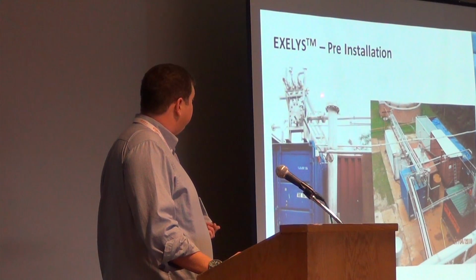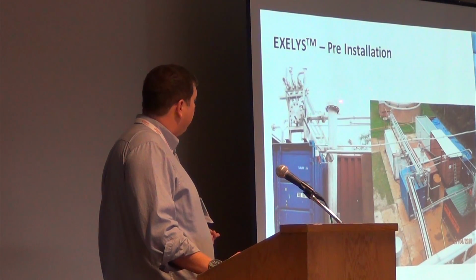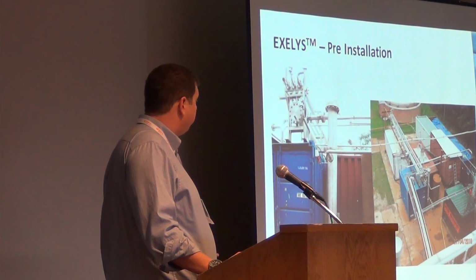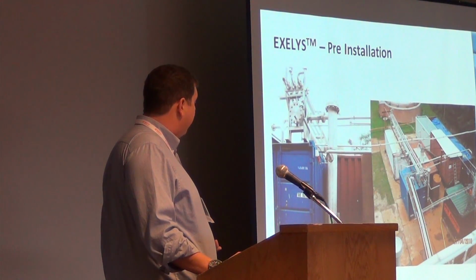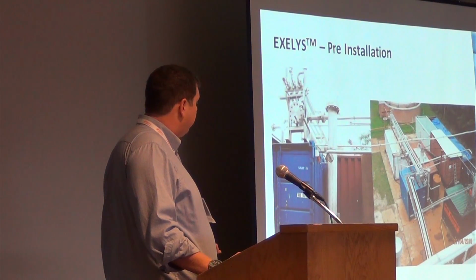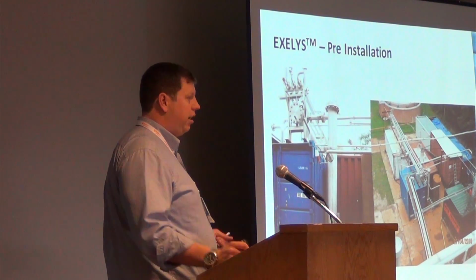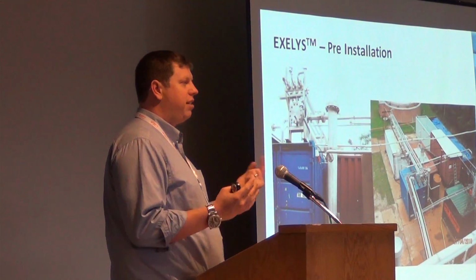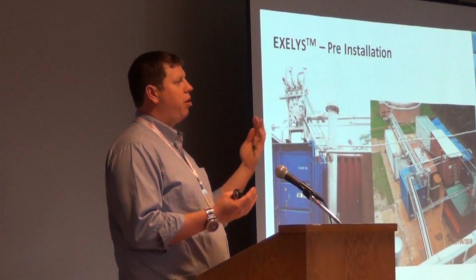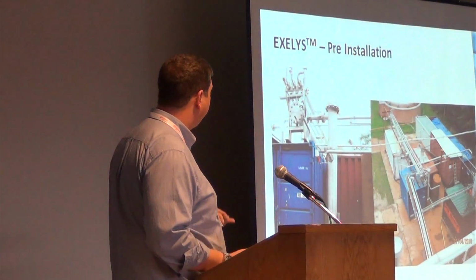This is the static mixer column here. As you can see, there's just a flange with a static screw inside. The steam comes down from the steam injector into this port, and they hook up through these nozzles here. The steam is injected through six nozzles, and it pushes the sludge up and hydrolyzes it as it goes up through the static mixer.